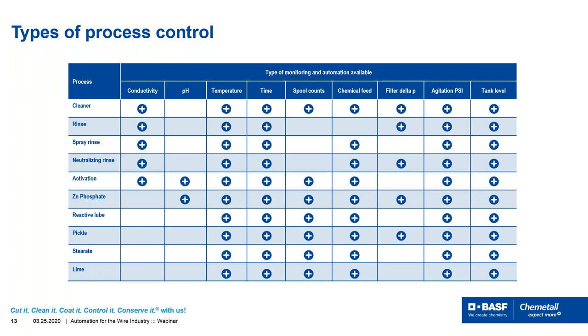Along with that, there's also the tank level, maintaining it at a certain amount. You may wonder why this is so important. The importance is because if someone makes a large addition of water, your chemical balance is going to change until the chemical feed pump can bring it back to the normal range. So if you can maintain your level within a certain delta, instead of noticing you're about 6 inches low and then filling it back up, you'll be able to maintain a tight delta. Your chemical feed will be minimal at any given time, and you'll have a uniform bath all the time.